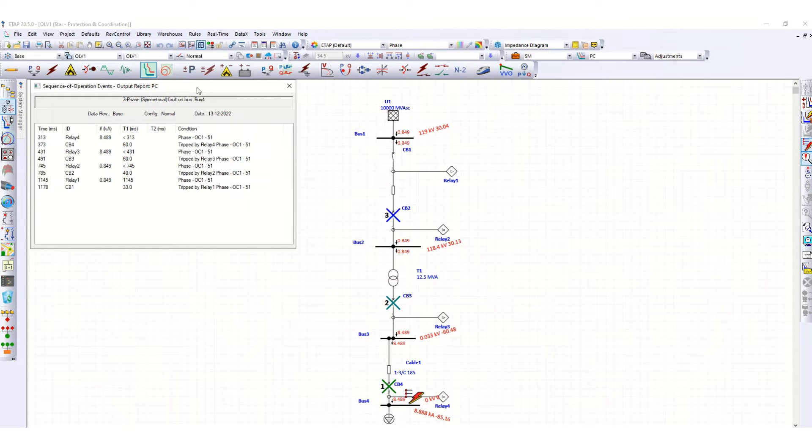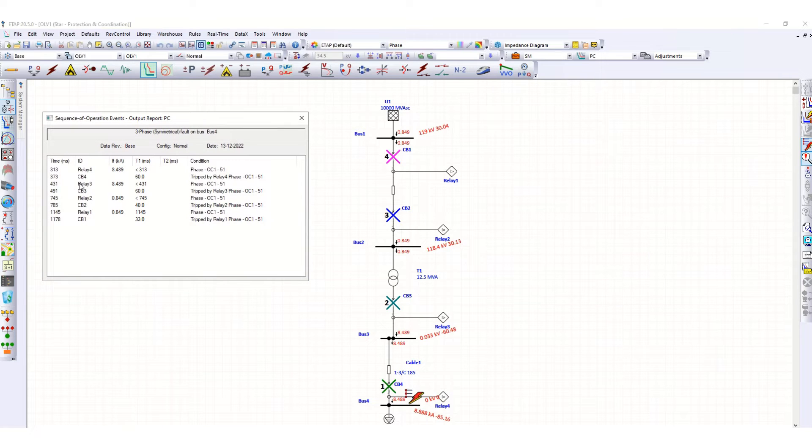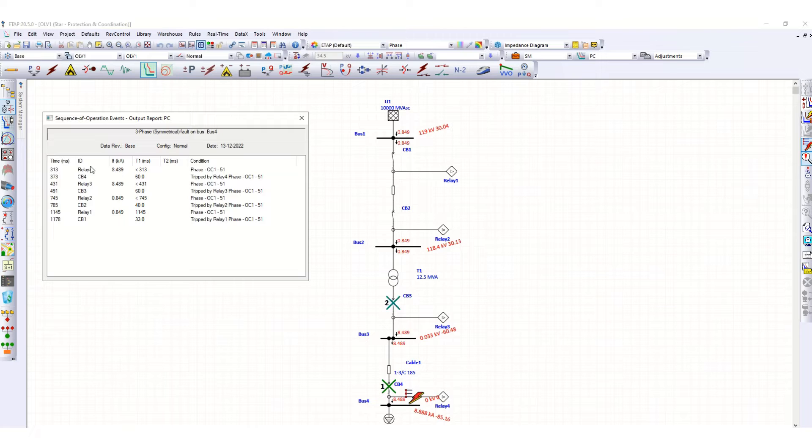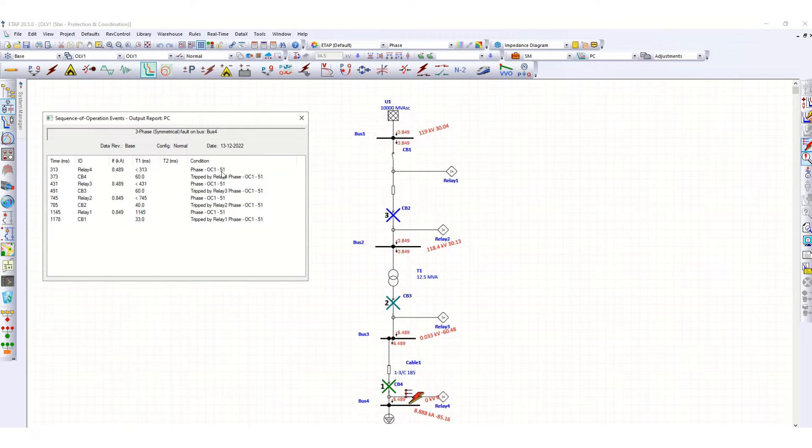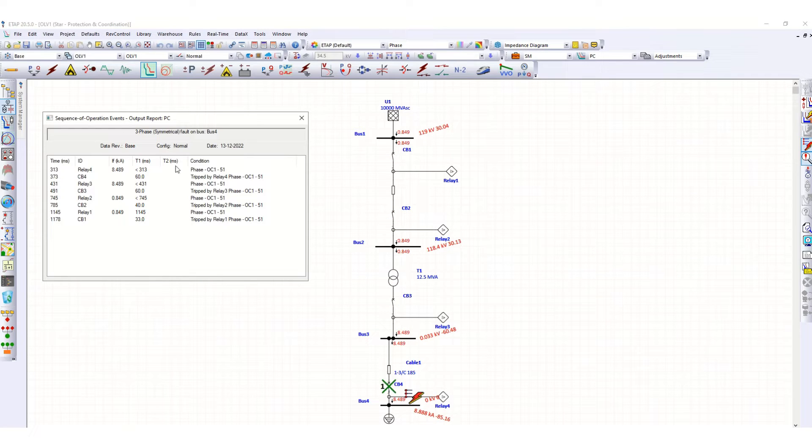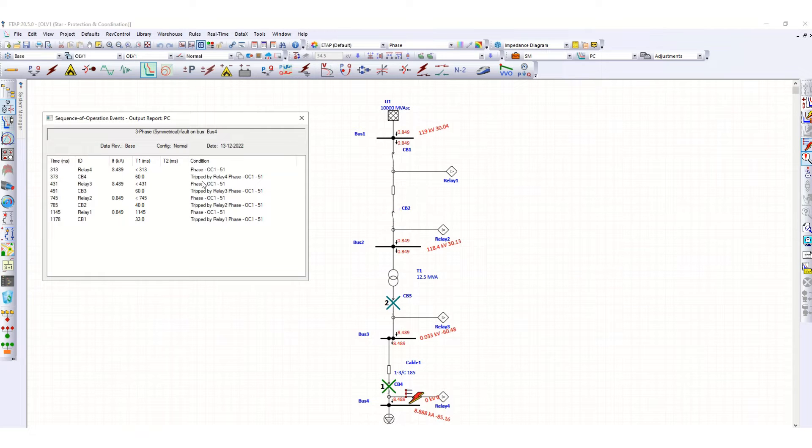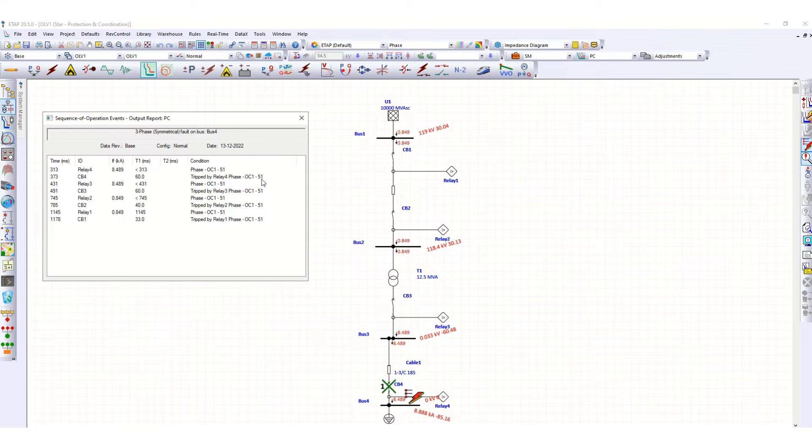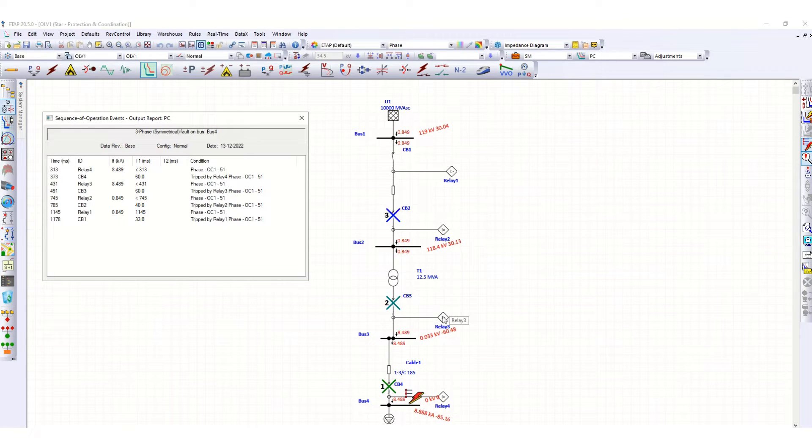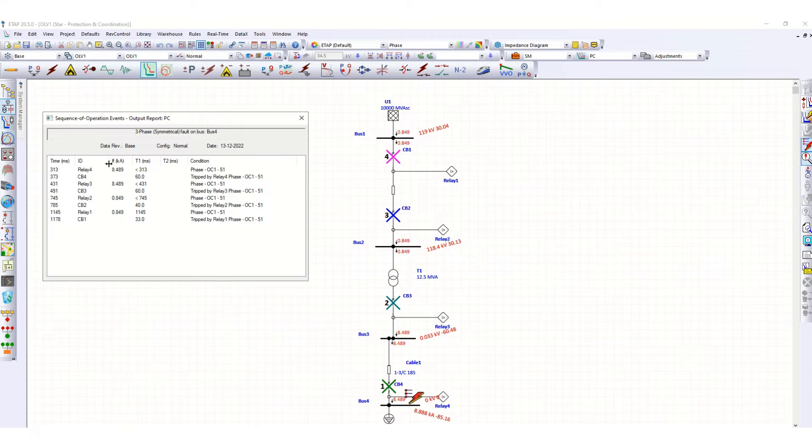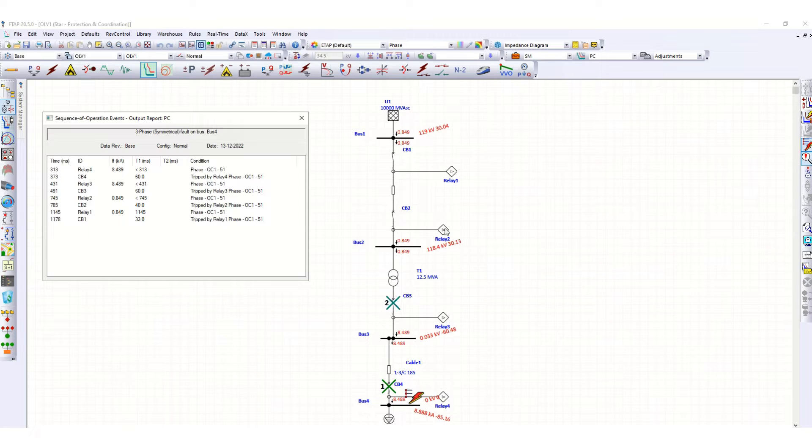If you see this relay 4, this overcurrent element 51 relay 4 is picking up and due to this, CB4 is tripped by relay 4 phase overcurrent 51. Then relay 3 and corresponding CB3 circuit breaker is tripped.